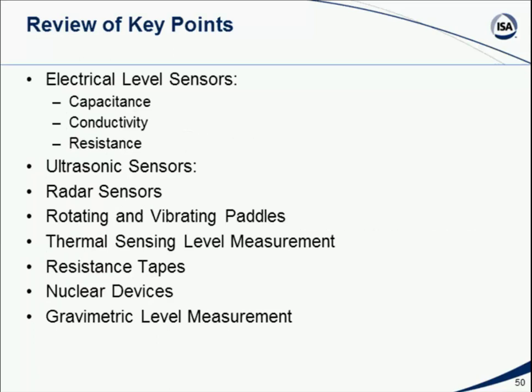So what did we talk about? We're discussing electrical means and electrical technologies for measuring level. We talked about electrical devices that change capacitance or conductivity or resistance. We talked about the use of active devices like ultrasonic and radar sensors that send out pulses and time them coming back. We talked about mechanical devices, electromechanical devices like thermal sensing and rotating paddle. We mentioned resistance tape. We discussed nuclear measurement device, the measurement of gamma rays as a way of identifying the rough level in the tank.